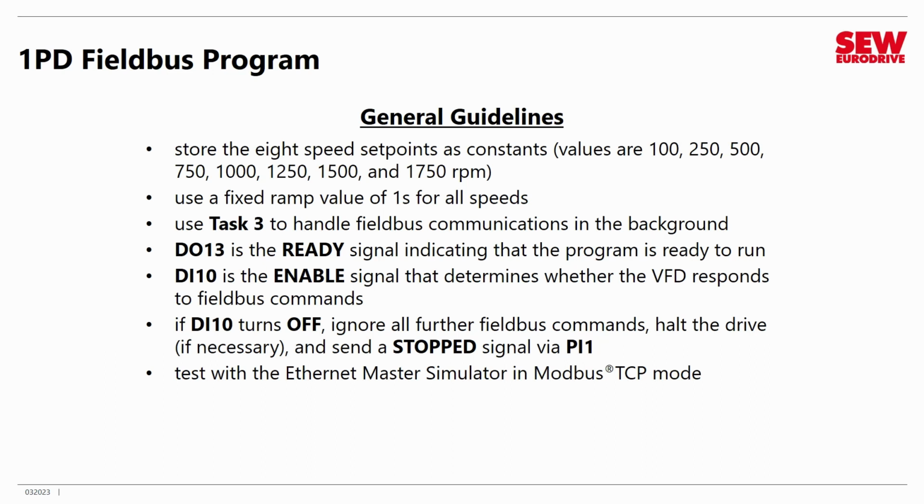We're going to test this with the Ethernet Master Simulator, and the way you need to do it is put it in Modbus TCP mode. If you put it in Ethernet IP mode, you can have some problems. So Modbus TCP is fine. If you've got a Fieldbus card that supports both the Modbus TCP and Ethernet IP, you're good.